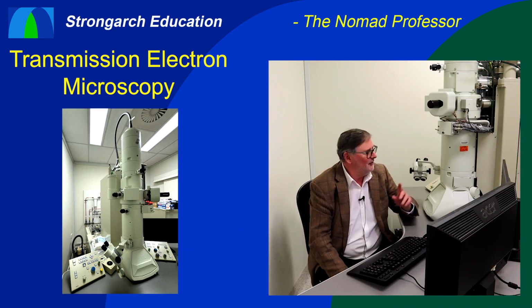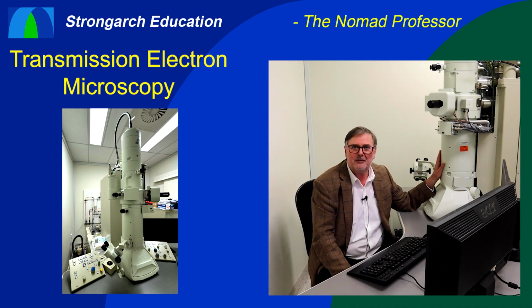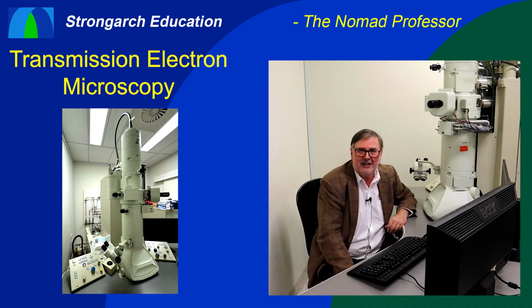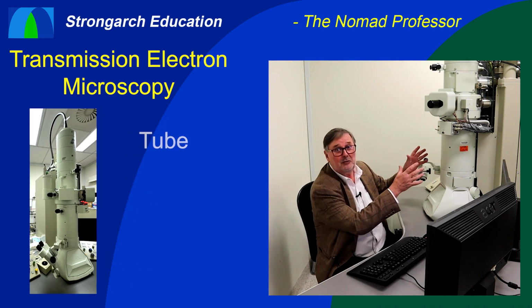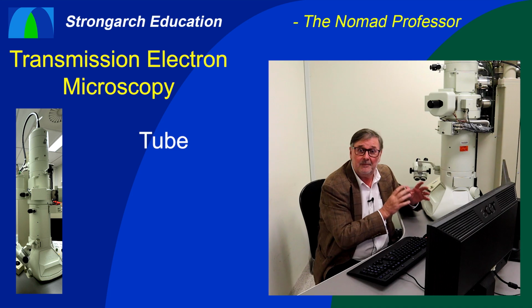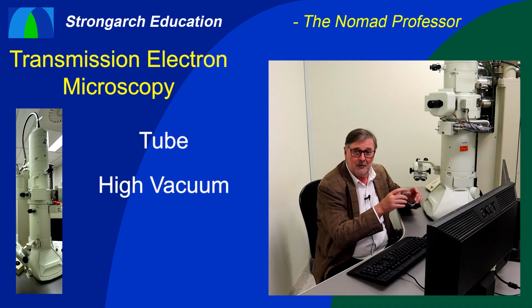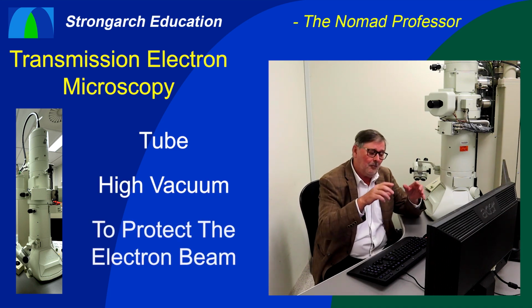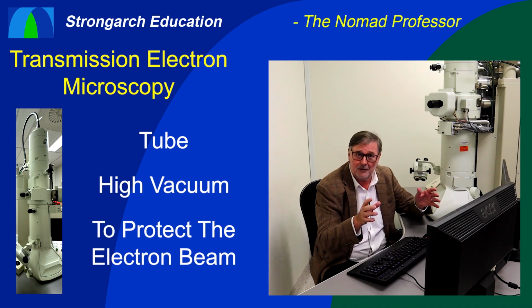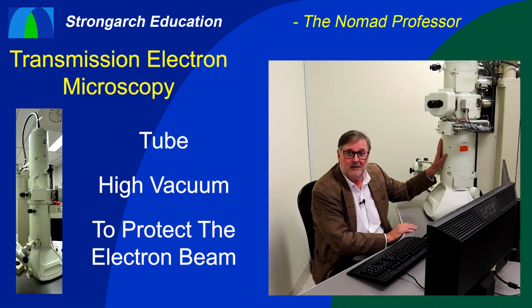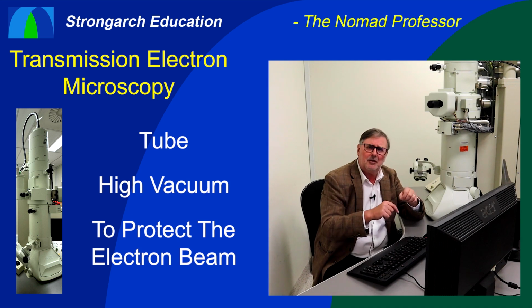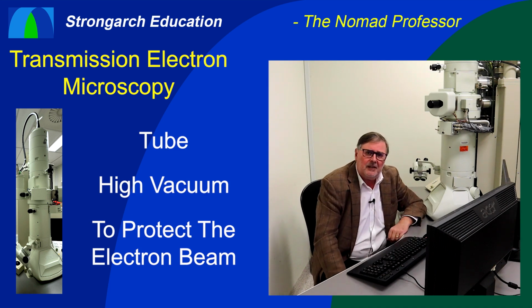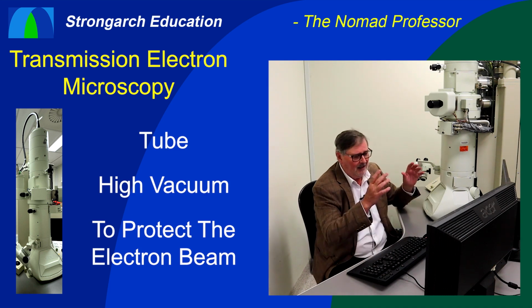Right, well, this is a transmission electron microscope. You can see it's much larger than a light microscope. Basically, it's a column, it's a tube, and it's kept under high vacuum because basically it's an electron beam. If there was any air, any gas at all inside of this tube, well, then the gas molecules would get in the way of the electron beam, and it just wouldn't work.